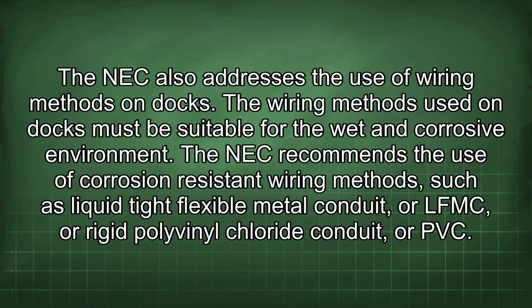The NEC also addresses the use of wiring methods on docks. The wiring methods used on docks must be suitable for the wet and corrosive environment. The NEC recommends the use of corrosion-resistant wiring methods such as liquid-tight flexible metal conduit, or LFMC, or rigid polyvinyl chloride conduit, or PVC.